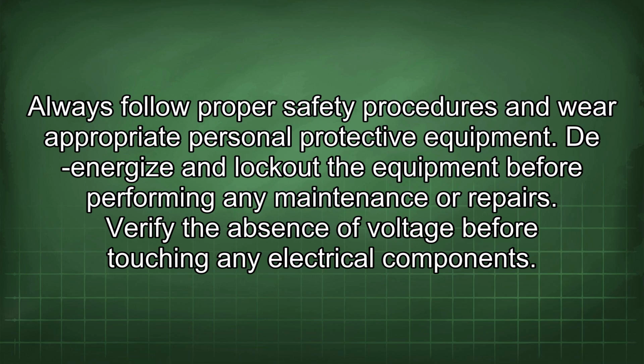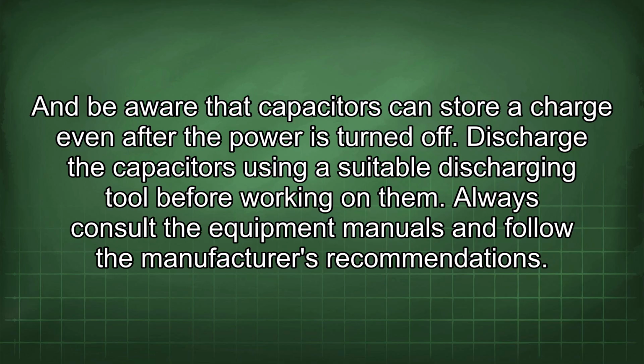De-energize and lock out the equipment before performing any maintenance or repairs. Verify the absence of voltage before touching any electrical components. And be aware that capacitors can store charge even after the power is turned off. Discharge the capacitors using a suitable discharging tool before working on them. Always consult the equipment manuals and follow the manufacturer's recommendations.